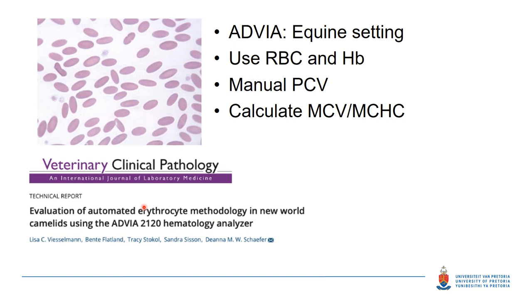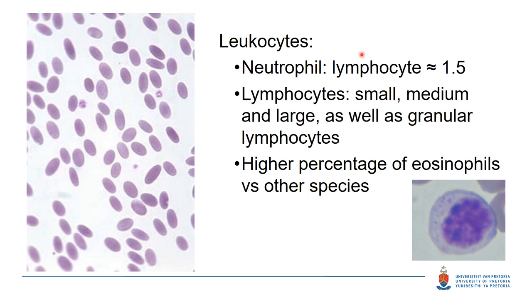A technical report looked at the best way of evaluating new-world camelid blood on the ADVIA 2120 hematology analyzer, and the authors found that the equine setting was best to use. Using the equine setting, you can use the red cell count and hemoglobin concentration from that, run a manual packed cell volume, and then calculate your red cell indices. Camelid settings on other analyzers may not be as well validated. In terms of leukocytes, camelids tend to have a lymphocytic leukogram with a neutrophil-to-lymphocyte ratio of about 1.5, and you may see granular lymphocytes. They also have a higher percentage of eosinophils than other species, so do not over-interpret moderately high eosinophil counts as eosinophilia.